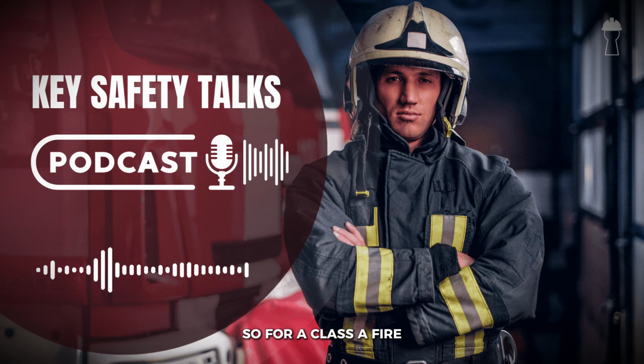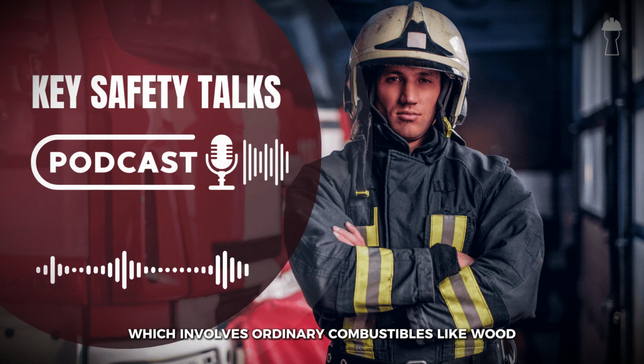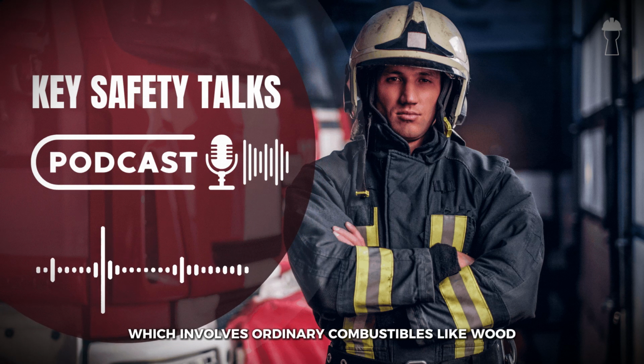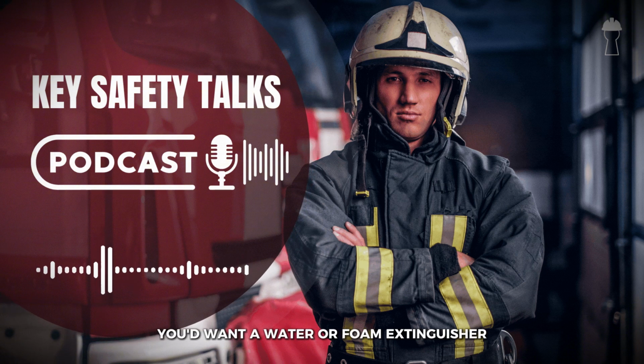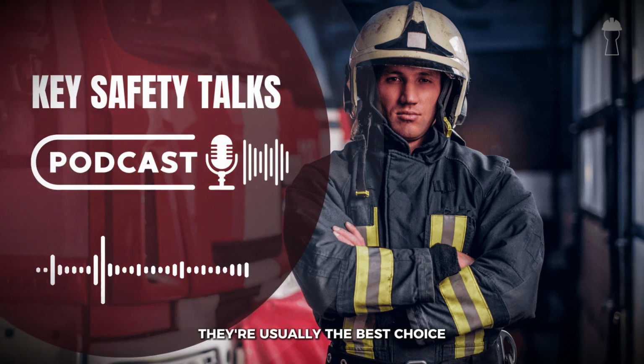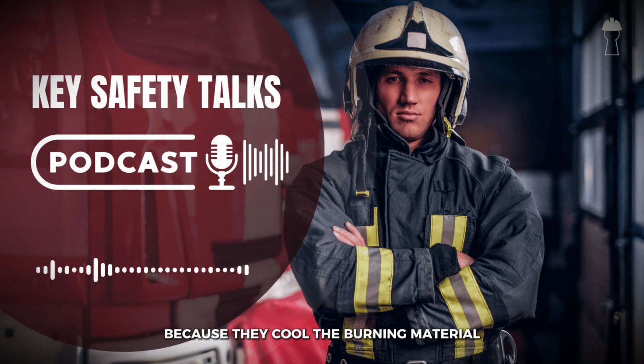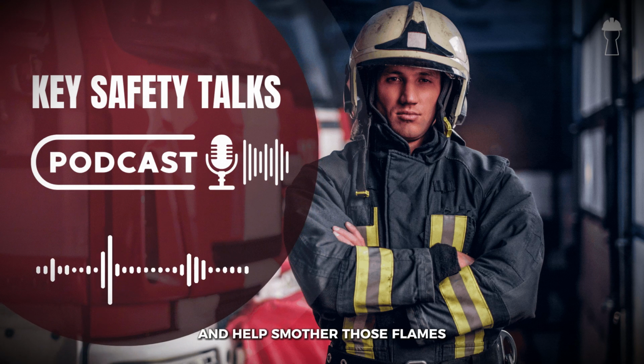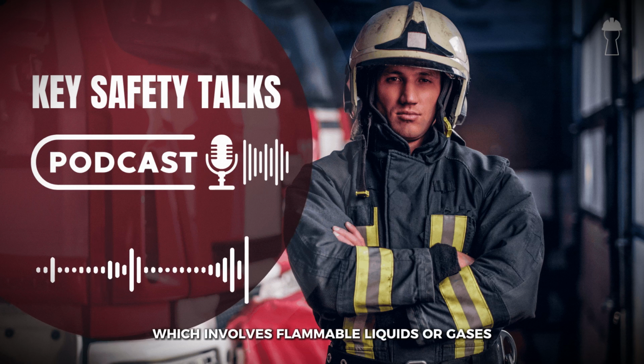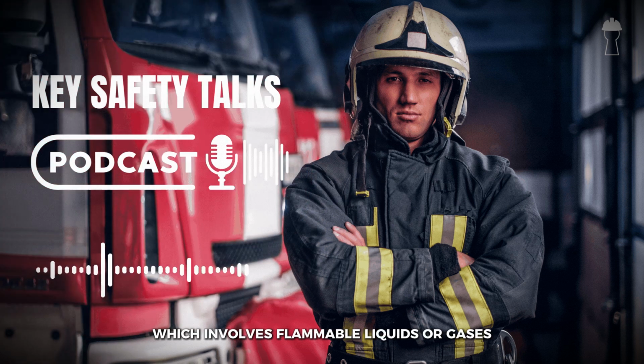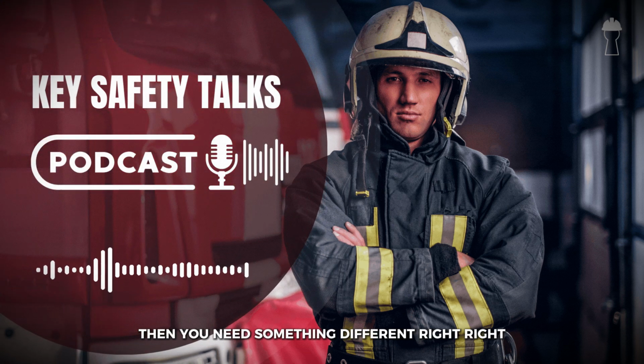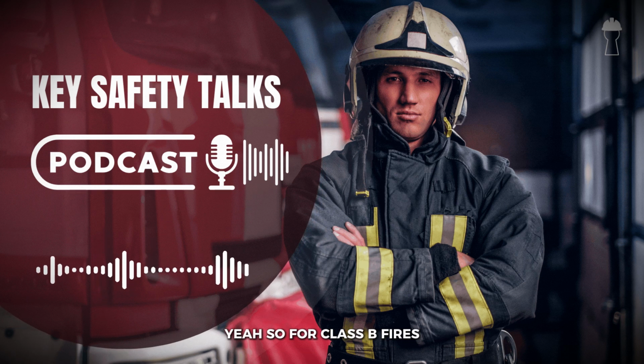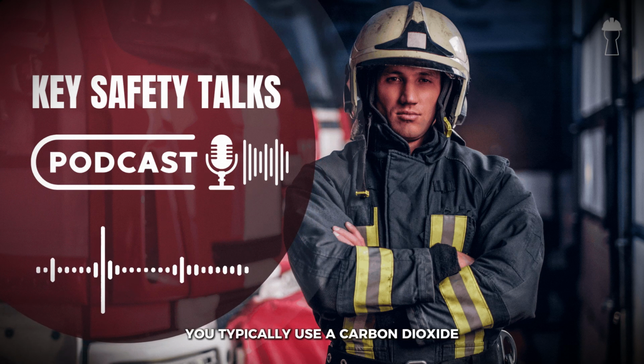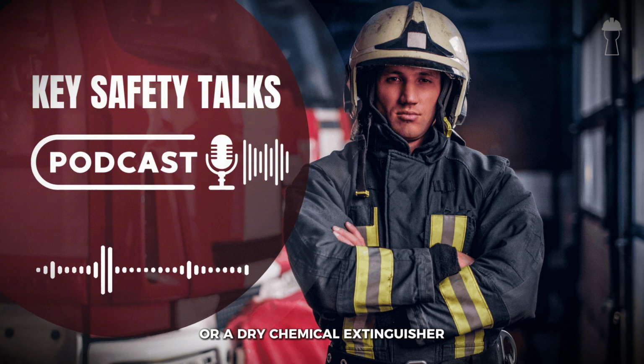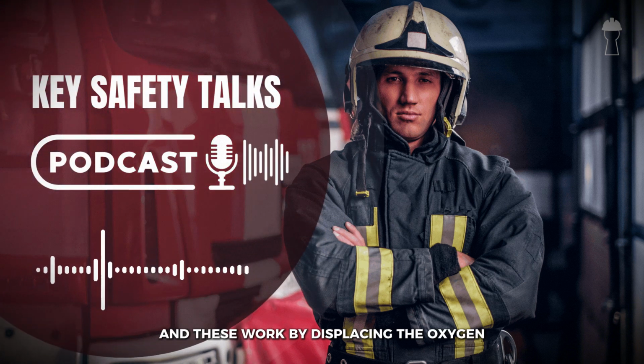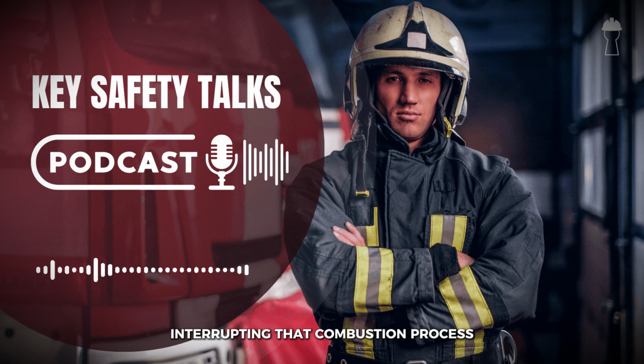Yeah, sure. So for a Class A fire, which involves ordinary combustibles like wood, paper, cloth, you'd want a water or foam extinguisher. They're usually the best choice because they cool the burning material and help smother those flames. But if you have a Class B fire, which involves flammable liquids or gases, then you need something different, right? Right. You need something specific for that. Yeah. So for Class B fires, you typically use a carbon dioxide or a dry chemical extinguisher. And these work by displacing the oxygen, interrupting that combustion process.